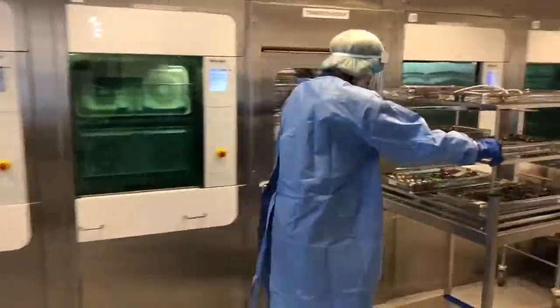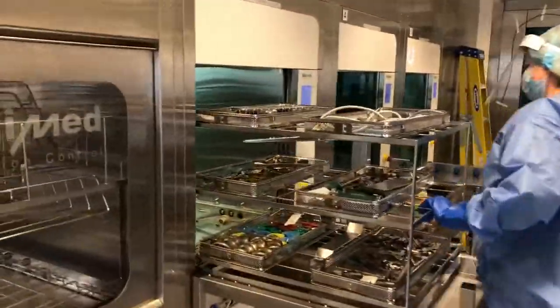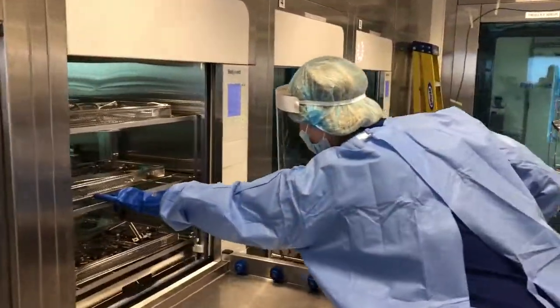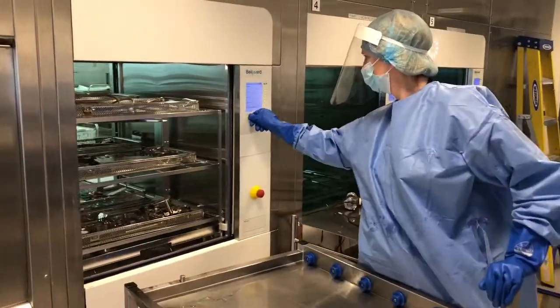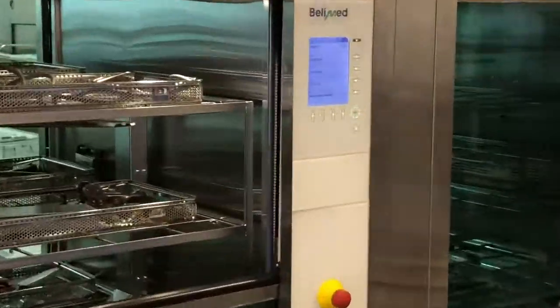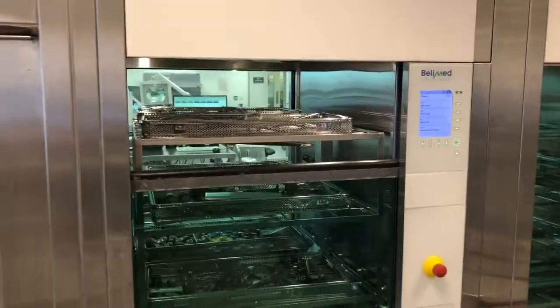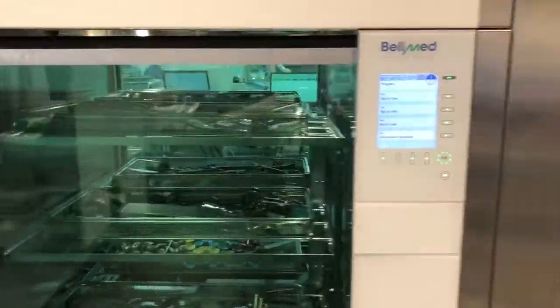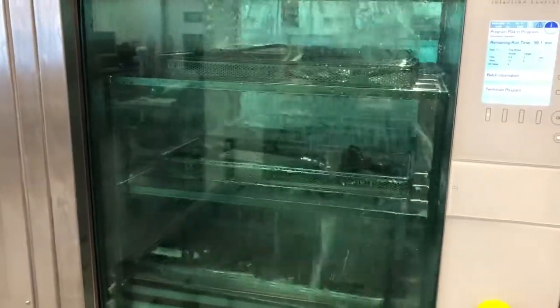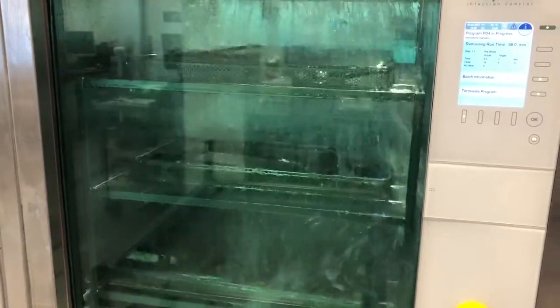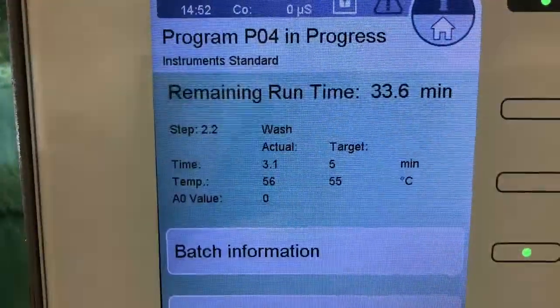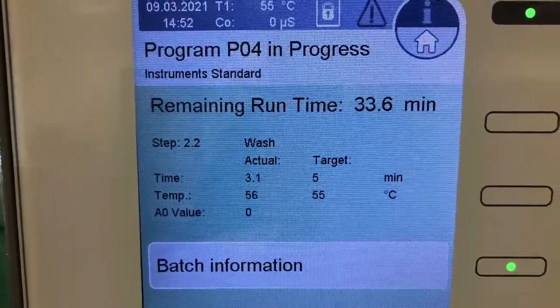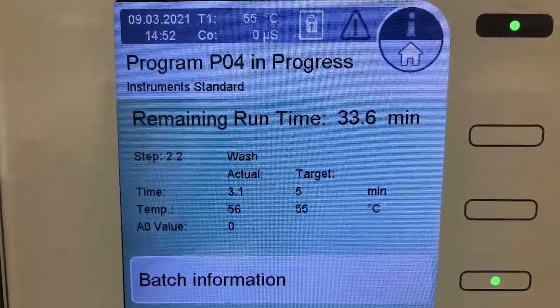The staff member will scan the equipment barcodes to a particular washing machine, load it onto racks, and then push it into the washer. The washer disinfector machines are very much like domestic dishwashers. However, they operate to strict criteria whereby instruments are washed to specific timescales and temperatures with detergent which are laid down in best practice guidance. Washers disinfect at a temperature of 92 degrees and a wash cycle takes approximately 45 minutes to complete.